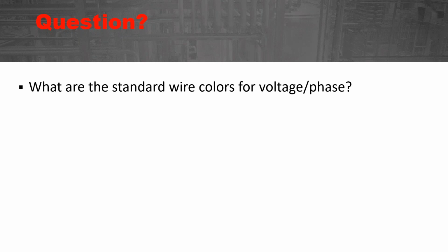Now, we do have requirements in the NEC. If you have a three-phase, four-wire delta connected system, the high leg has to be color-coded orange. If you use blue color wire in an intrinsically safe system, you cannot use blue otherwise. But we have to be careful of these industry standard colors. I have heard that there's a plant in North Carolina and other places as well where those industry standard colors are exactly opposite of normal. An electrical contractor coming in as a contractor, the host is going to have to let them know, we have something here that is not standard. So they have to tell them about the color coding that is in that plant.